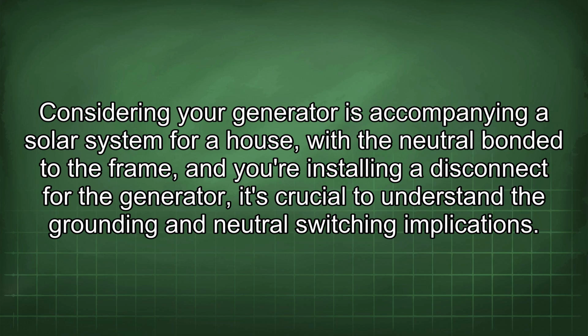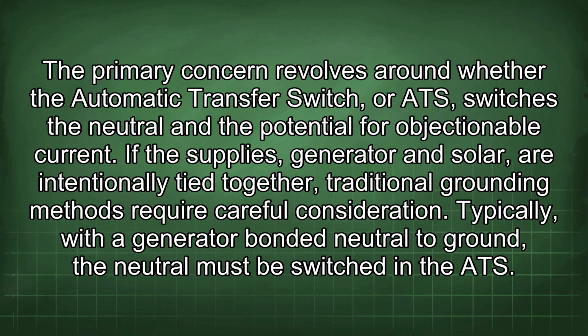Considering your generator is accompanying a solar system for a house, with the neutral bonded to the frame, and you're installing a disconnect for the generator, it's crucial to understand the grounding and neutral switching implications. The primary concern revolves around whether the automatic transfer switch, or ATS, switches the neutral and the potential for objectionable current. If the supplies, generator and solar, are intentionally tied together, traditional grounding methods require careful consideration.